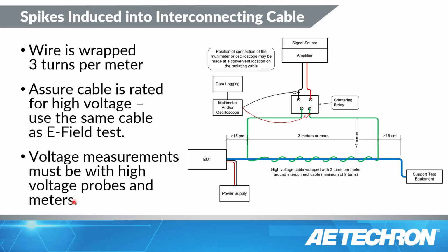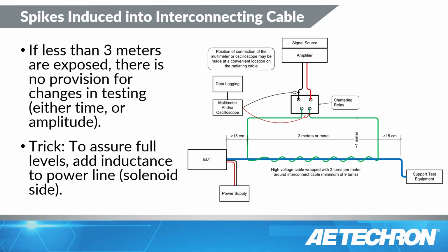Again, the voltage measurements you're making here are fairly high voltage. So assure that your voltage probes are rated for that high a voltage. Most oscilloscope probes are only rated for 300 volts. Make sure you're using one that will measure at least 1,000 volts. Now, finally, there are two things to notice. I talked about earlier what happens if you use a shorter cable here? Well, there's no relaxation to this test. You can't drop the voltage. How would you drop the voltage to begin with? Can you use less exposed cable? Well, you'll have to for a shorter cable to begin with, and that will automatically drop the voltage down. But unfortunately, you have to do the test with the levels that are given to you.